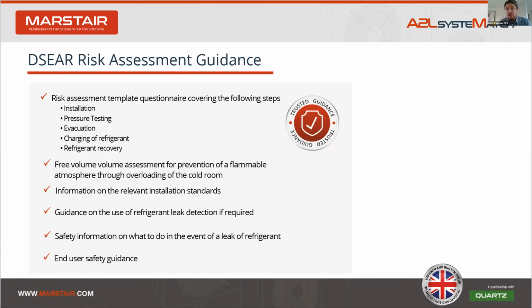Okay, risk assessments. It's important to point out that we've worked with independent consultants who are experts in the field. What does this mean? It means we provide an installation risk assessment template within our instructions, covering all aspects of the installation. We also provide the free volume guidance that we showed earlier, for which we've used EN 60079-10-1. Through the assessment of factors such as the potential leak rate of refrigerant, the free volume requirement has been calculated. We also provide other guidance, including what to do with leak detection, alarms, and what to do in the event of a refrigerant leak.